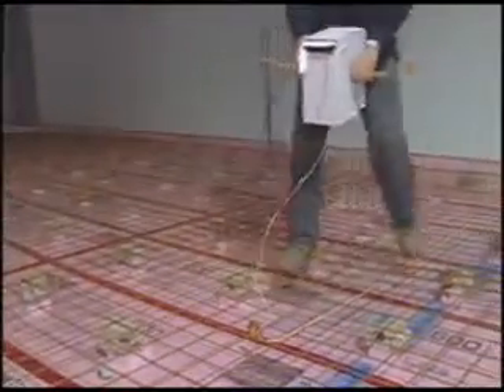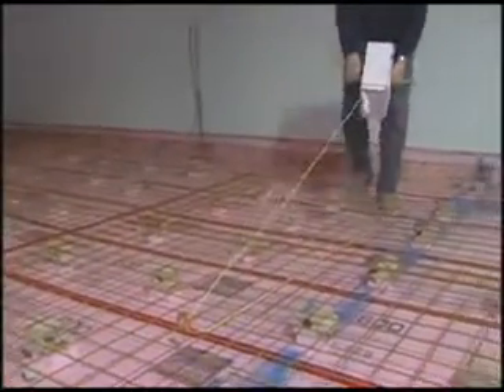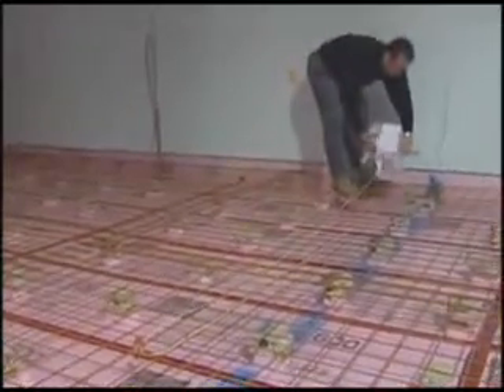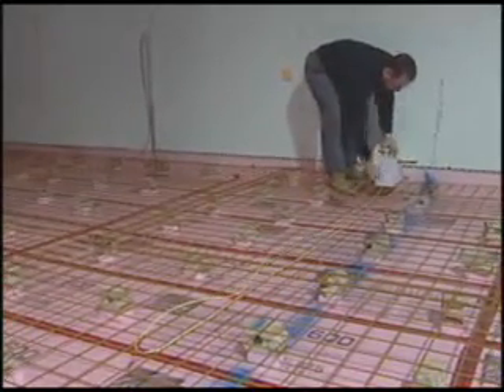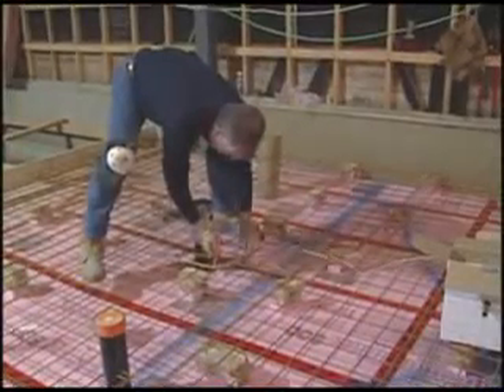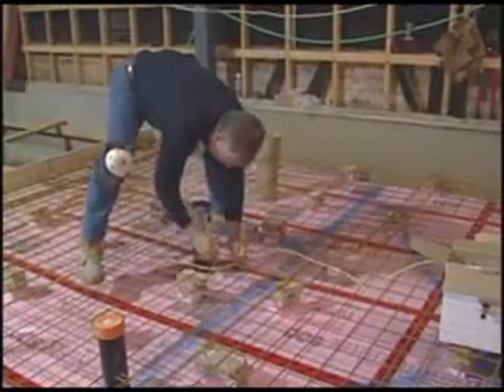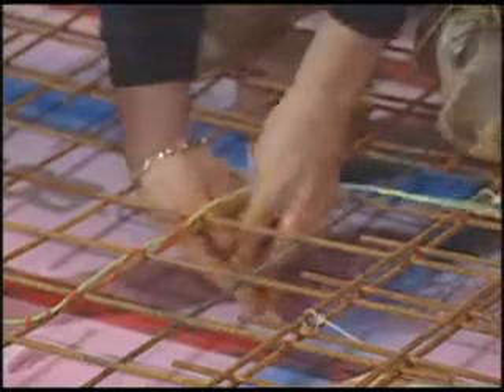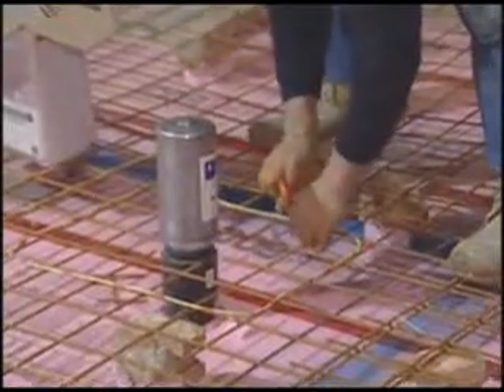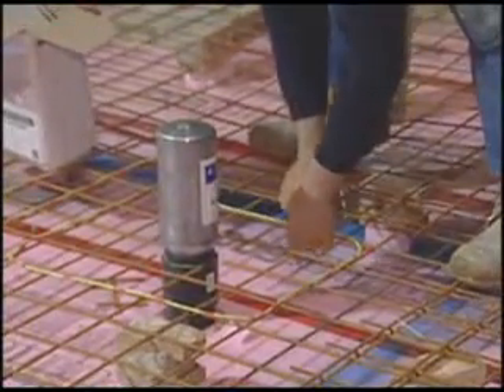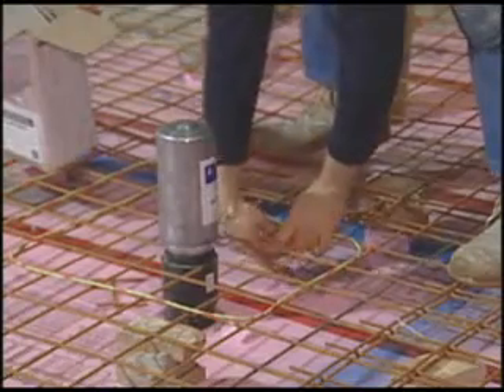When the cable is attached to the mesh and the end of a run of cable has been reached, the cable must curve so it can return in the opposite direction for the next run. Work around obstacles by attaching the cable to the mesh so it follows the outline of each one. When it becomes impossible to leave enough space for a return run, change the direction of the cable.